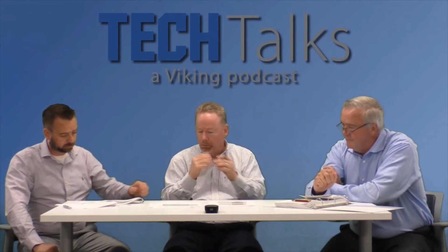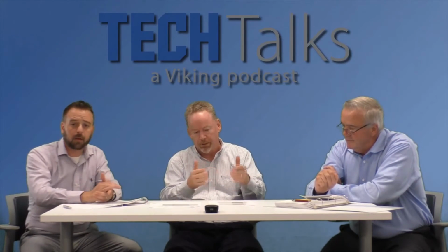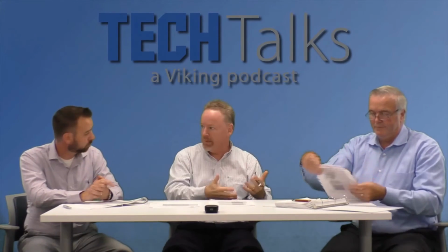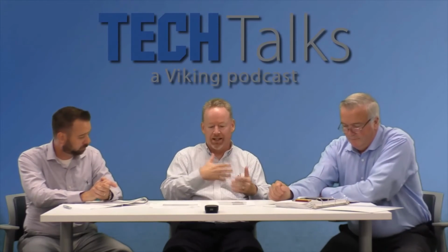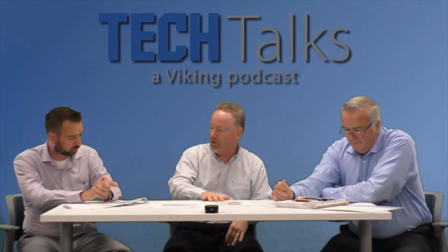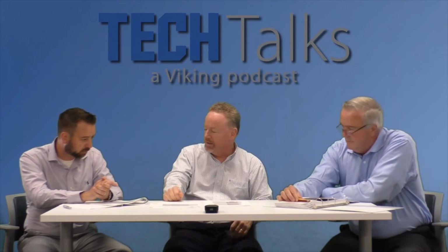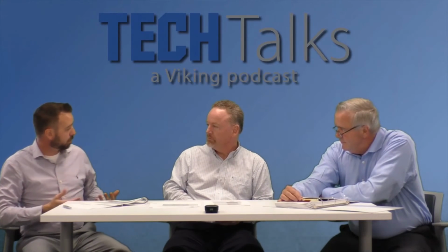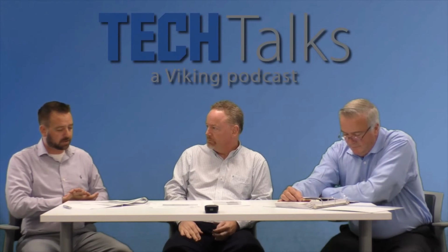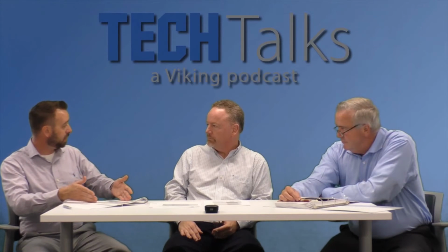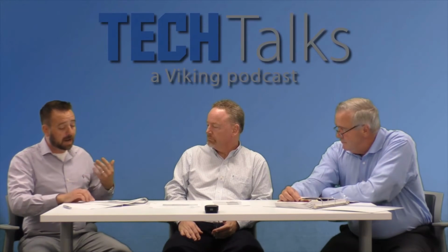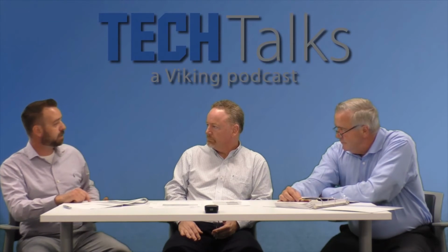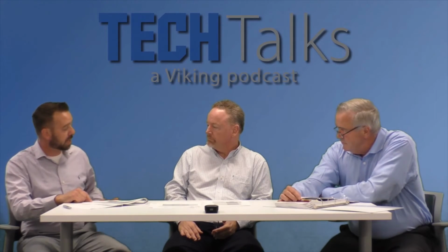So why don't you walk us through, what we're going to do now is in the white paper, we've got 4 figures that go through the results of actually, not theoretical now, but actually calculating it and where we all wind up. So why don't you walk us through your calc process on this and what you came up with? So in the figures, we just show the branch lines and the sizes of the branch lines, but what we used for the calculations was a 40,000 square foot grid, for table 17B at 50-foot elevation. And we used 175 PSI starting pressure at the base of the riser for the static pressure.